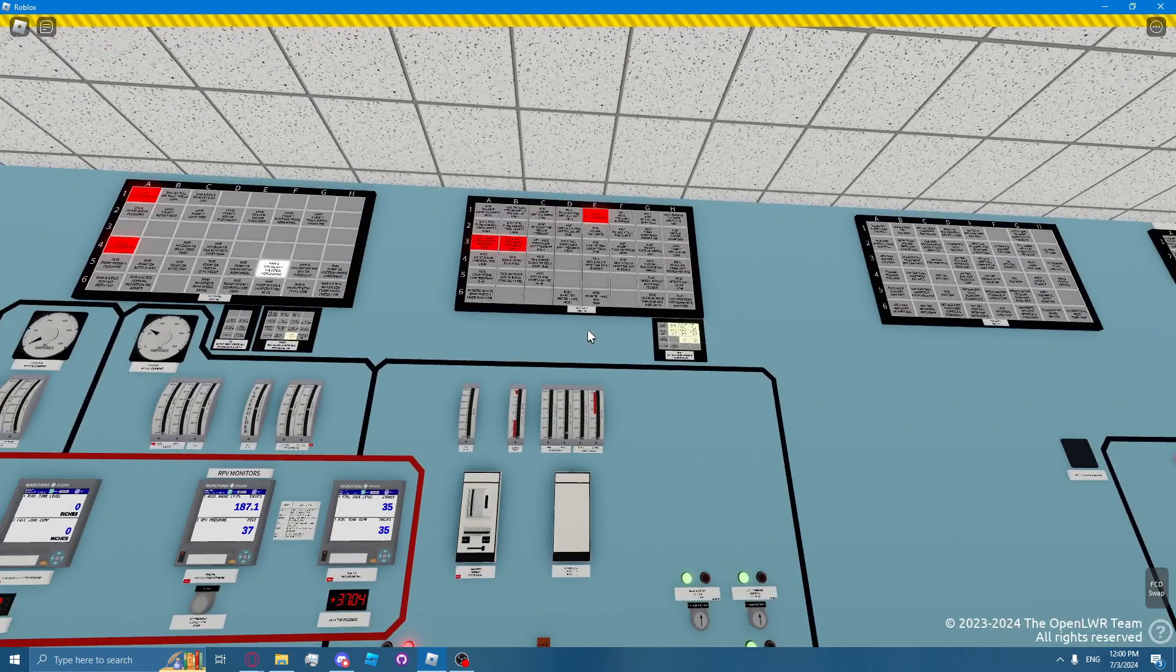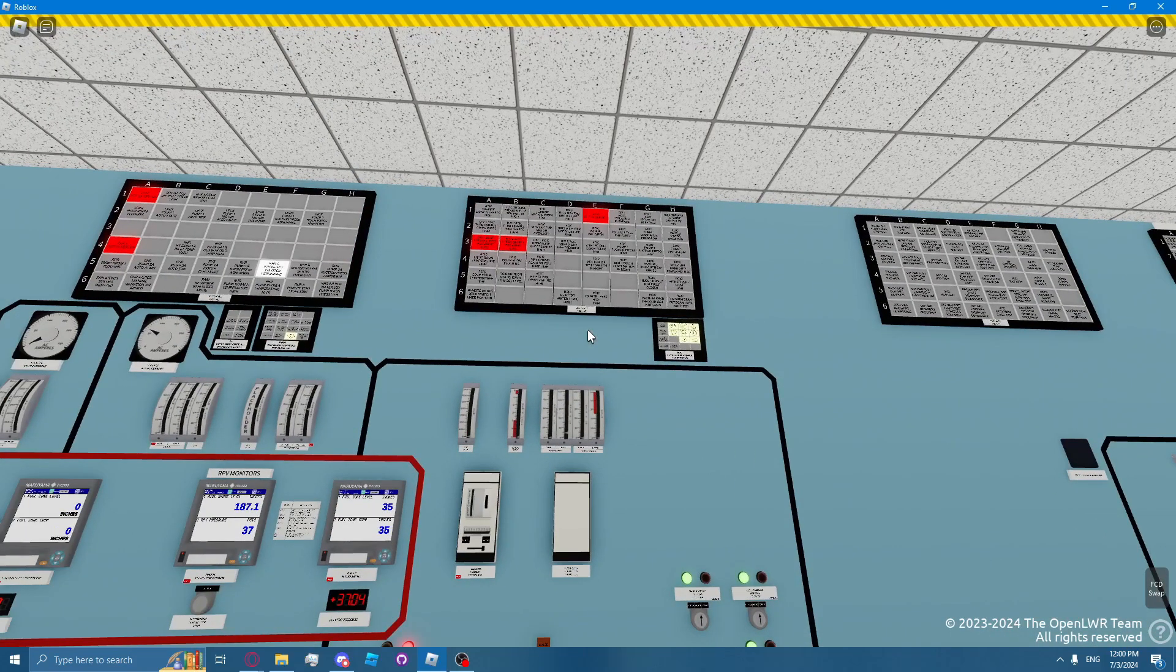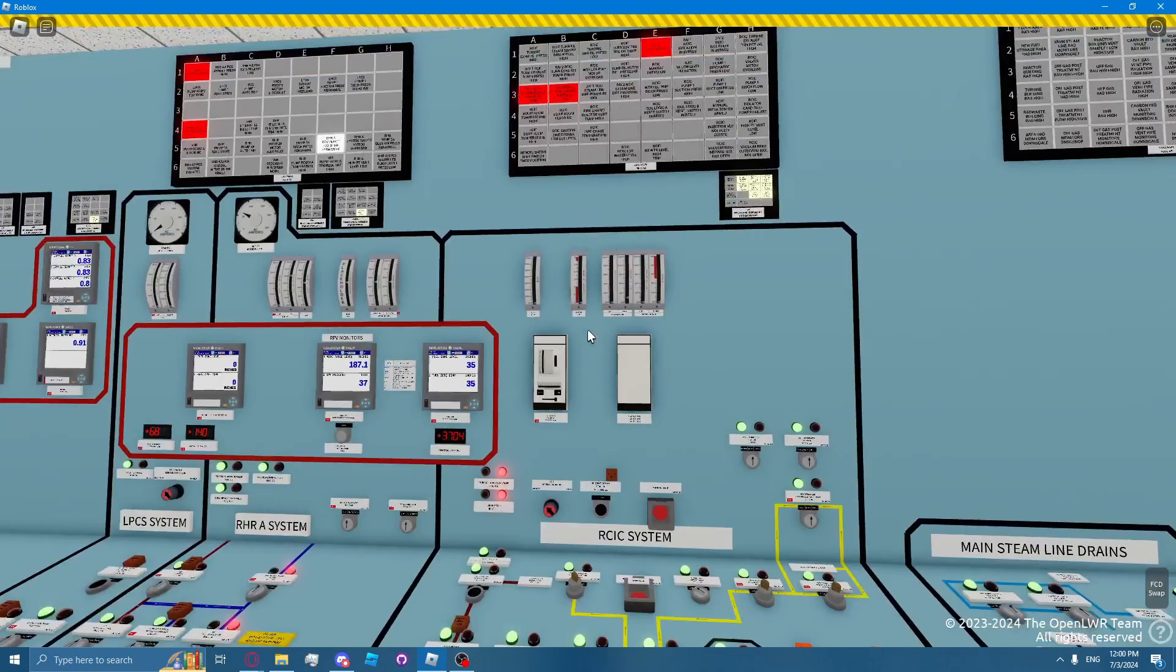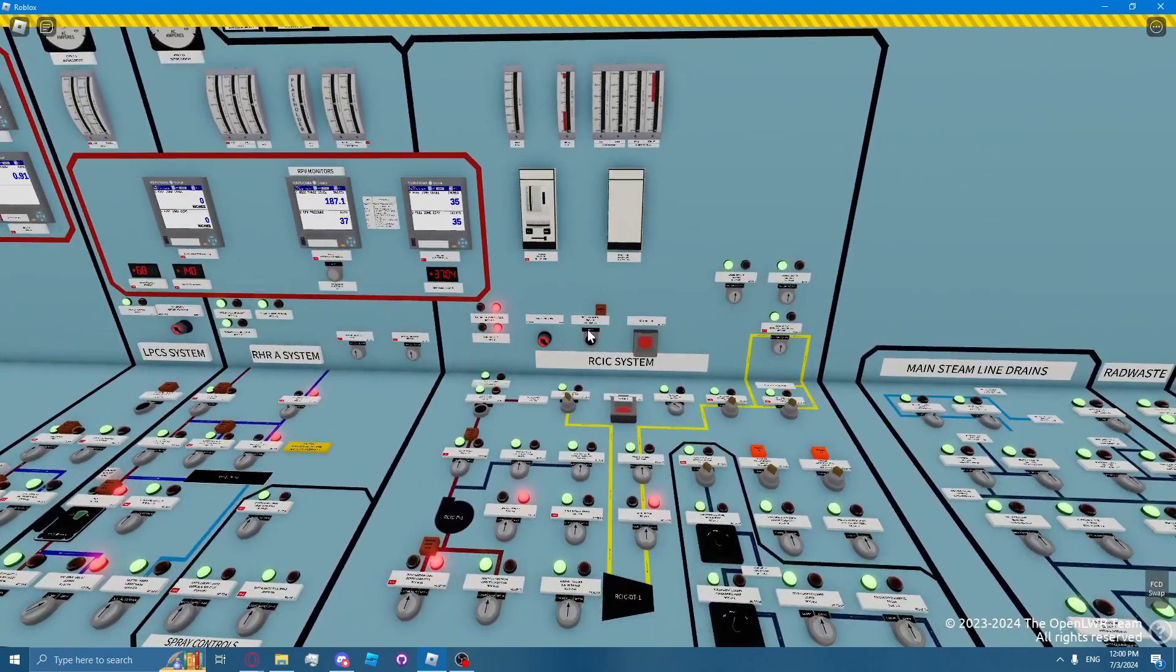The RCIC system valves are driven by DC power. This makes RCIC a credible system for inventory makeup during a station blackout.